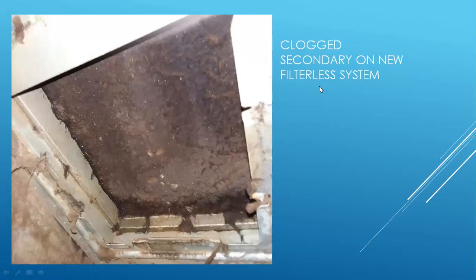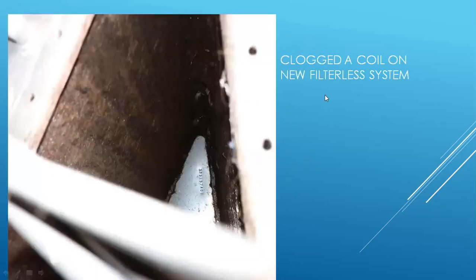That there is also part of the new filterless system that the customer was sold, and that is the secondary heat exchanger on a 90% furnace. It's hard to even tell what it is, but if you look closely, you can see your blower racks right here, and that's your secondary. That's horrible. And again, this is the same system, and this is the A coil. So you can imagine that the system was not heating, it wasn't cooling. The customer paid a decent amount for this system, and I'm thinking this is like a year and a half, something like that old. This is what they got, and they were told that they didn't need a filter.